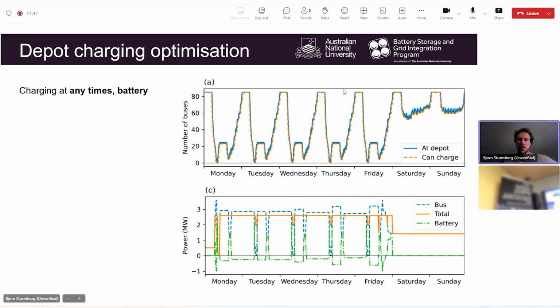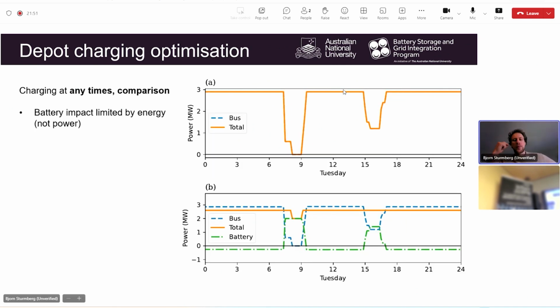You can see the impact best on this next plot, which is the same results but zoomed in on just one day's data, for Tuesday. The top plot is the power without a battery, and the bottom graph is the scenario with the battery. You can see distinctly how the battery is charging during the times when the buses are on the road, creating a very flat profile, which is efficient loading of the network, but it hasn't been able to reduce the peak demand on the grid by very much. That's because the battery is limited in its energy capacity, which in this example is 4 megawatt hours, and spreading that out across the whole day has only a modest impact on peak power.